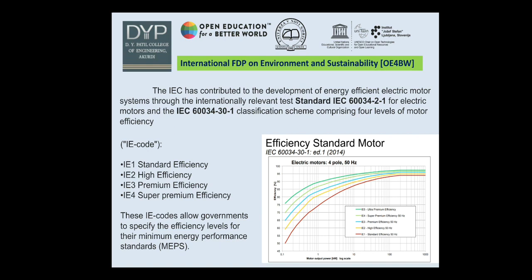Countries that are using these efficient motors: the European Union set motor MEPS levels. The European Union uses IE3 motors, that is premium efficiency motors, in combination, and they also use IE2. Then in USA they use IE2, and after 2007 they started using IE3, that is NEMA premium efficiency motors. Then in Australia and New Zealand they use IE2 from 2000, and in China they decided in 2002 to use IE1, IE2 and IE3. In Japan they use JIS, the Japanese Industrial Standard in collaboration with IEC efficiency. They use IE2 and IE3 level motors, and in India we use IE2 level motors, where IE2 means high efficiency motors.